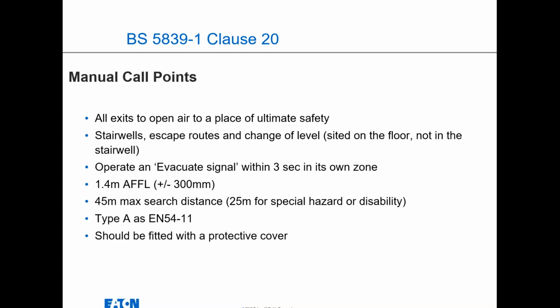Manual call points, which we touched on earlier, have their own little standards for how you install them. This is more about the installation factors: about 1.4 meters above finished floor level, plus or minus 300 mil. That's to comply with the Disability Act. Again, if you're in a wheelchair, you can't have a call point too high up because you couldn't reach it. Search distances within the space should be a maximum of 45 meters. Again, we touched on that for the fire brigade in terms of 60 meters for finding a fire within a zone. And nowadays, which is critical, they should all be fitted with a protective cover.